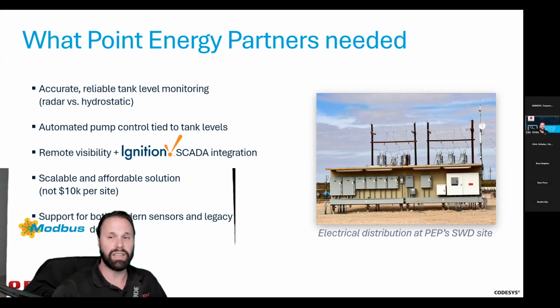Finally, legacy support was a must. They still had older sensors and transmitters running both Modbus RTU serial and Modbus TCP communication, so the new solution had to bridge those old legacy serial and Ethernet protocols with newer IIoT friendly protocols like OPC UA and MQTT Sparkplug B. That's the checklist they were working from.